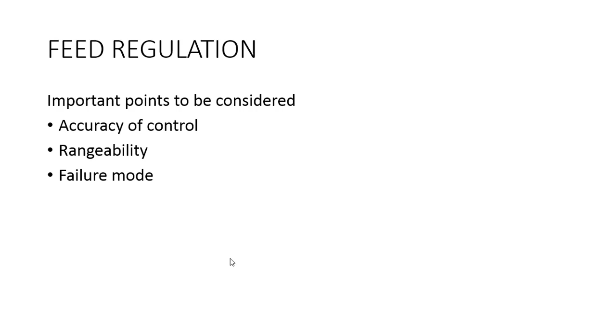Third is the failure mode. The fail-safe condition is considered as fail last for such an application. It means any actuator can be used, either pneumatic, electrical or even hydraulic. However, in a nuclear power plant it should be fail close to eliminate an uncontrolled leakage path, while the auxiliary feed water system takes control. Next is the continuous letdown valve.